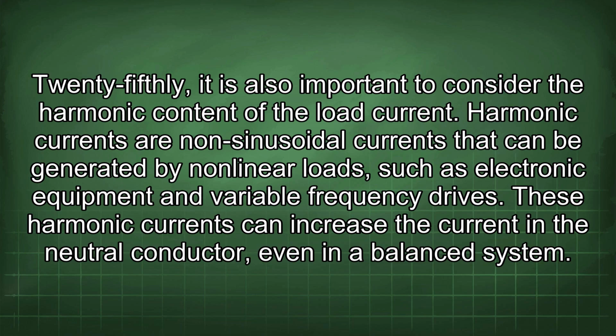25thly, it is also important to consider the harmonic content of the load current. Harmonic currents are non-sinusoidal currents that can be generated by nonlinear loads such as electronic equipment and variable frequency drives. These harmonic currents can increase the current in the neutral conductor even in a balanced system.